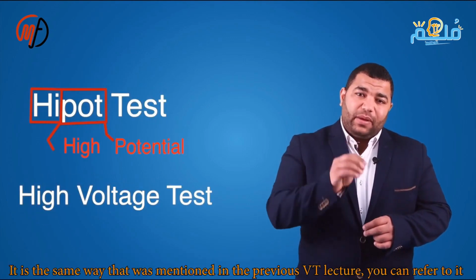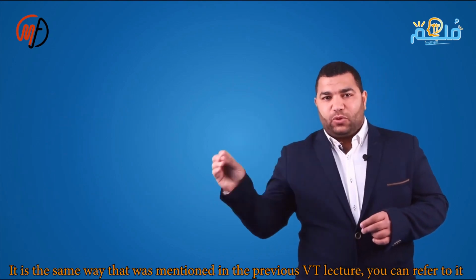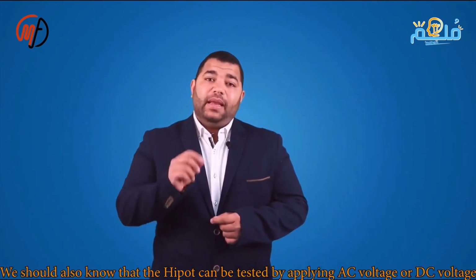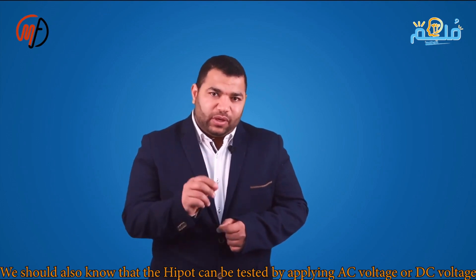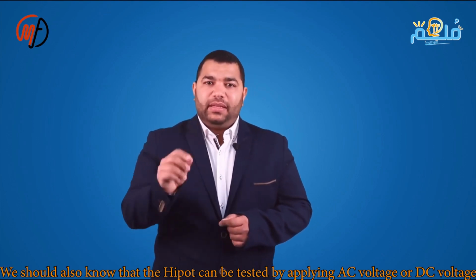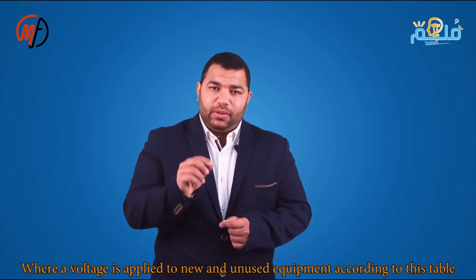For instance, to test a bus bar rated at 30.8 kV, apply 62.6 kV for 1 minute, calculated as 30.8 multiplied by 2 plus 1 kV. For DC, apply 106.4 kV, calculated as the AC voltage multiplied by 1.7.